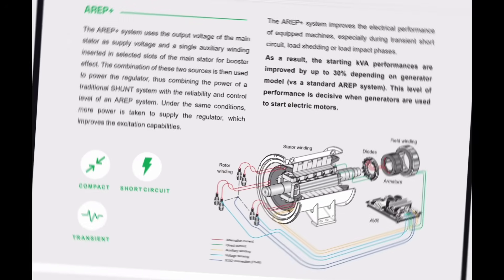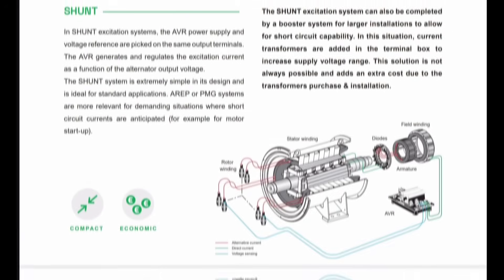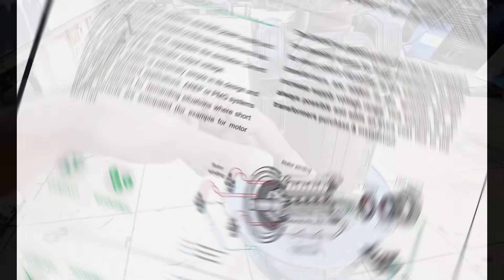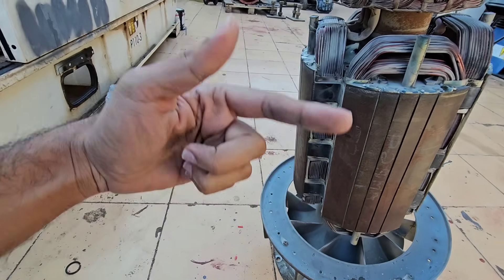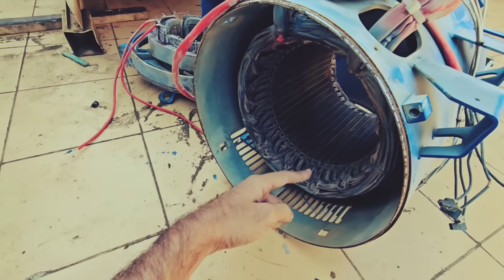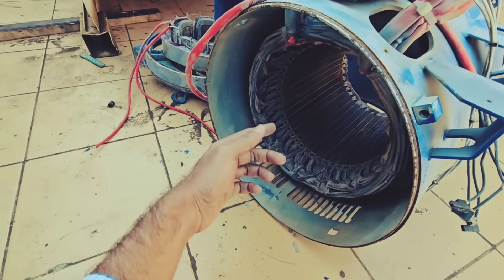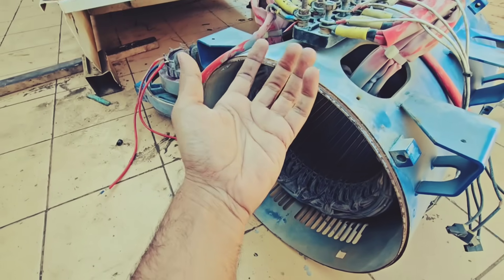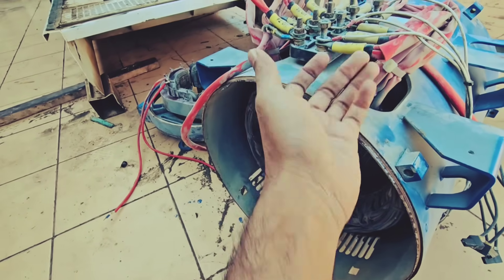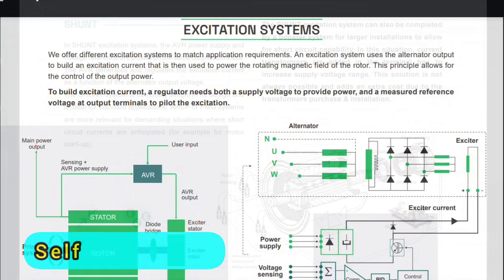Let's start from the basics. The excitation system is the most important part of any alternator because without excitation, no alternator can generate electricity. Its main job is to provide current to the rotor winding or field winding to create a magnetic field inside the alternator. This magnetic field is what generates electricity in the stator winding through electromagnetic induction. The current flowing inside the rotor winding is always DC current, never AC.